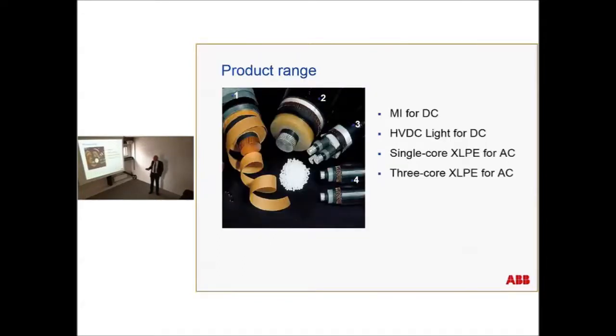The product range here is, we talked about the mass impregnated cable, which is paper lapped, paper insulation. Then it's impregnated in a resin at high temperature, and this is stable up to a maximum temperature of 60 to 70 degrees. Then we have what we call the extruded HVDC Light cable for HVDC here. We have the single core XLPE for AC, and we have the three core for lower voltages for AC.